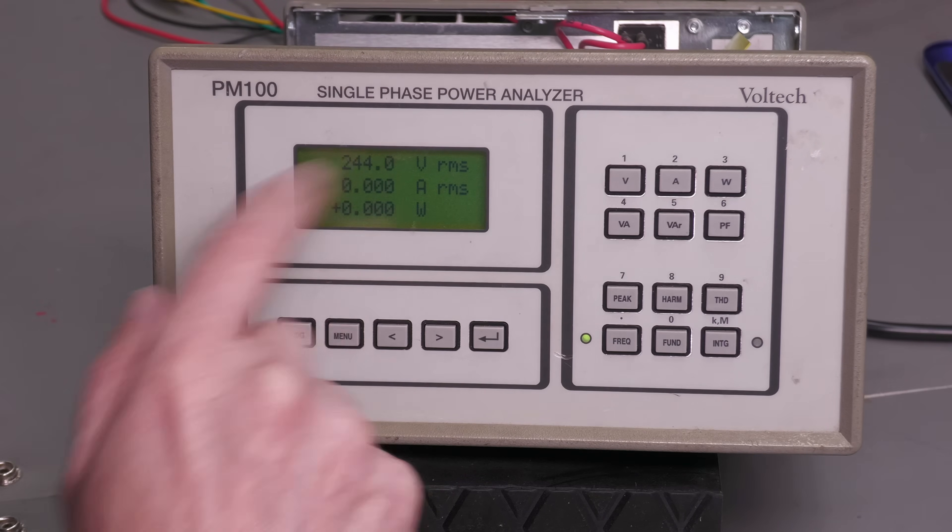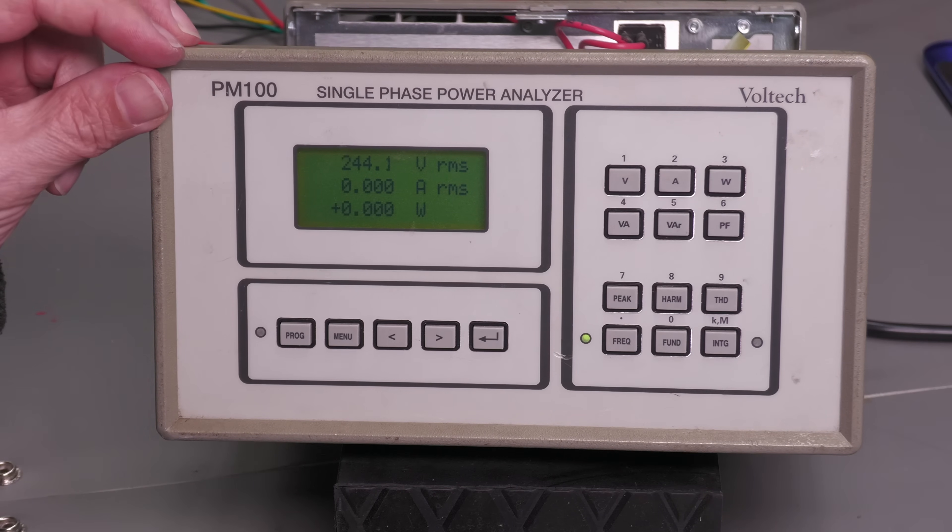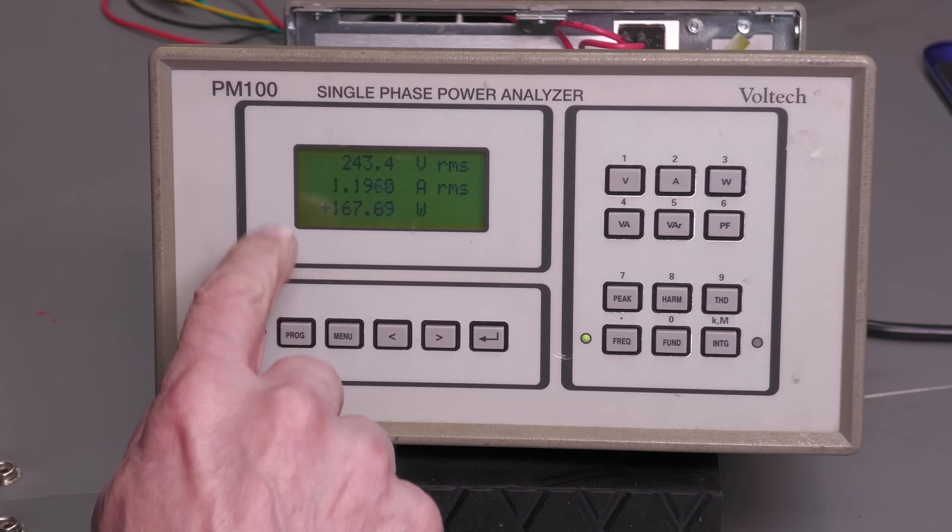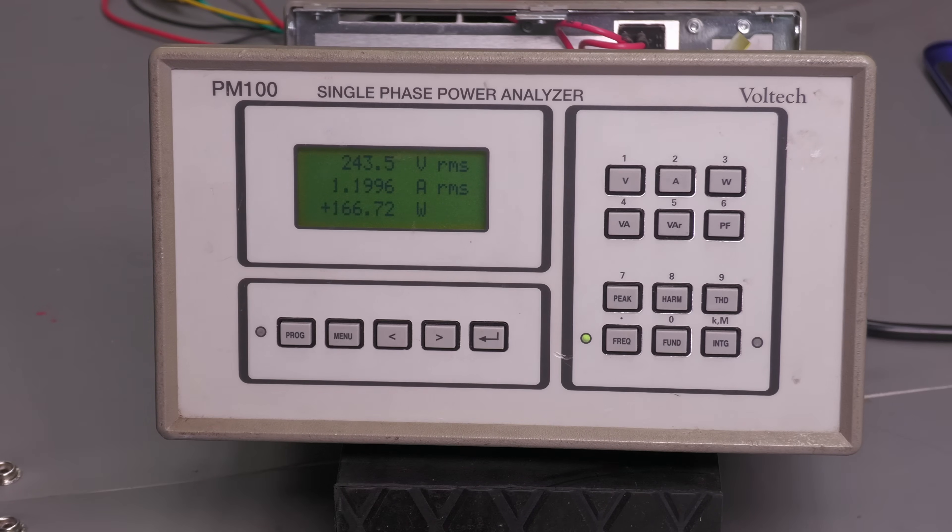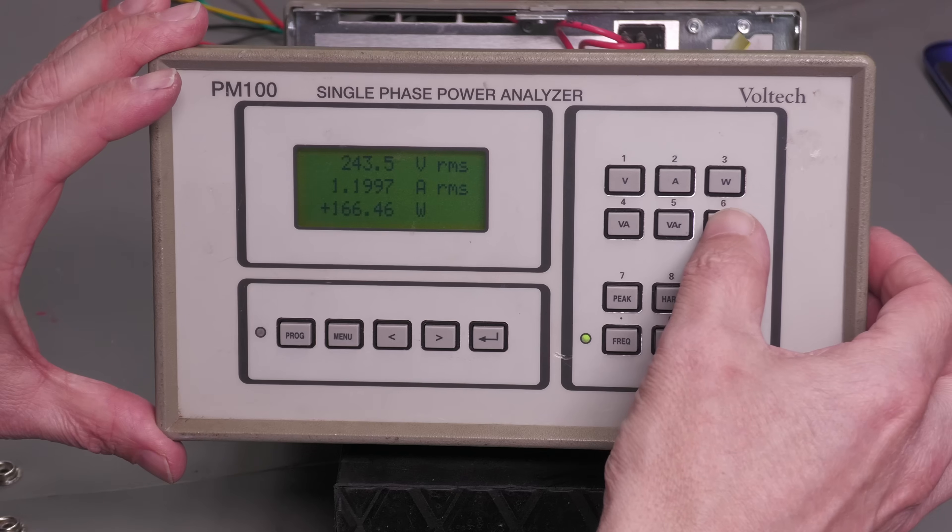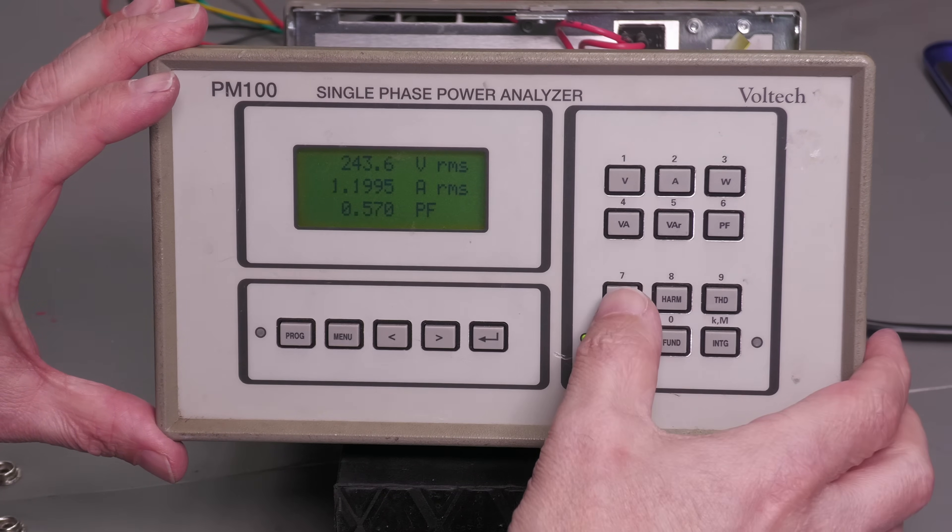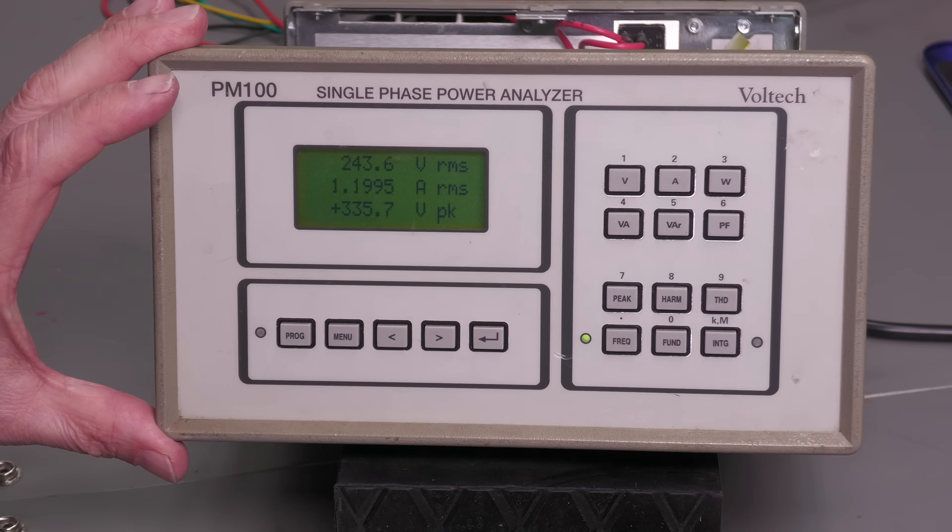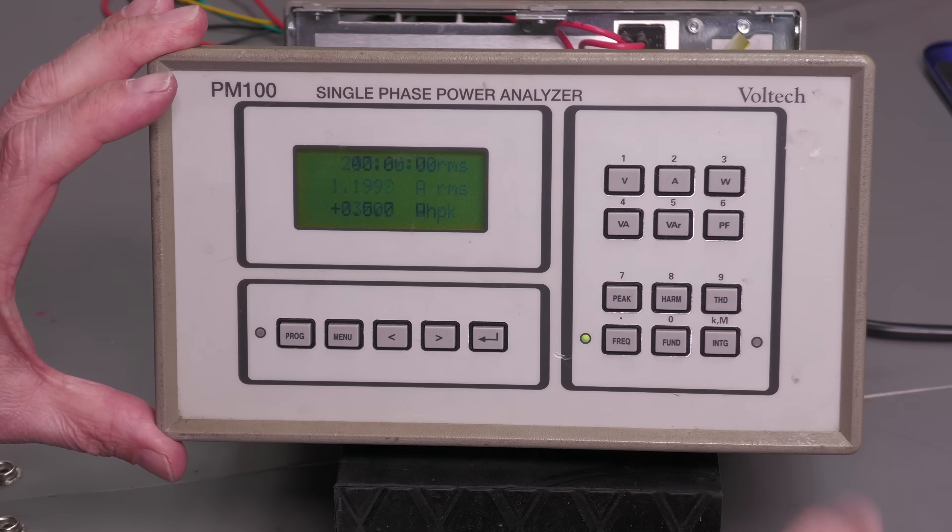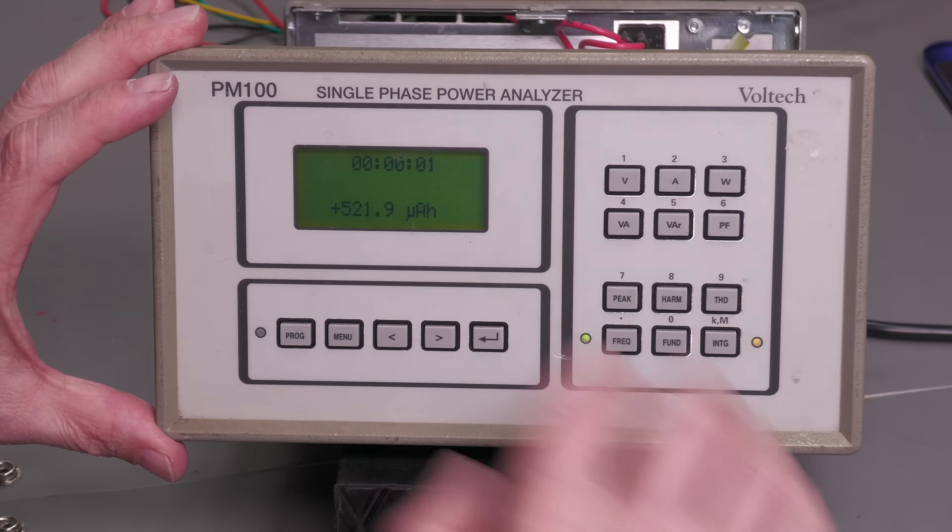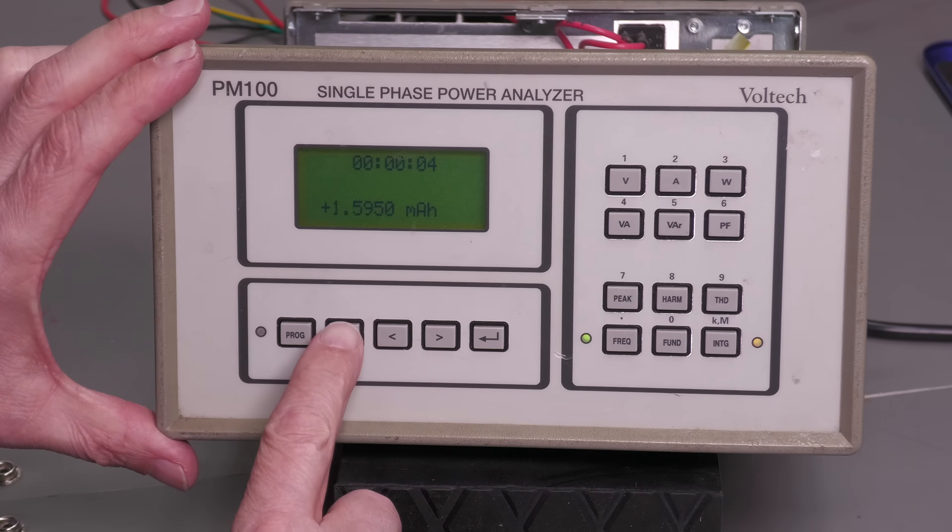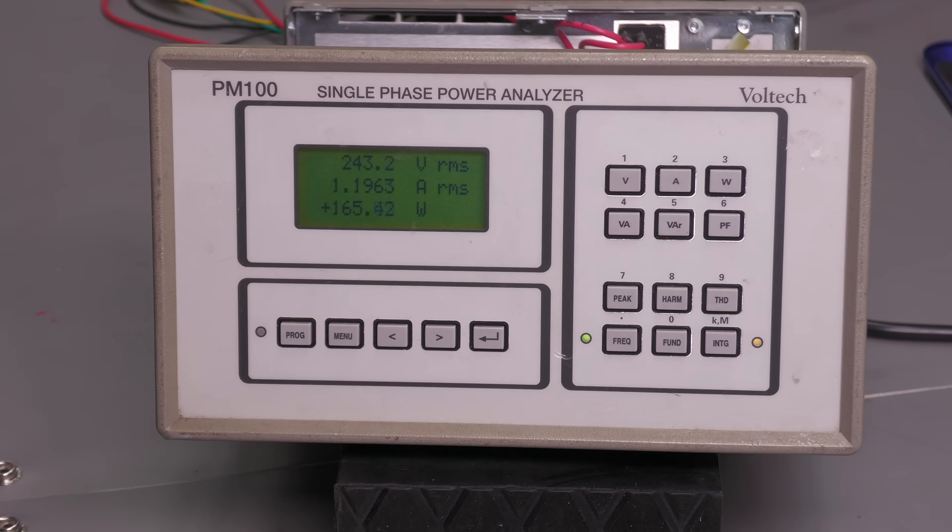244.0 volts today. So let me just switch on the heat gun. And yes, 1.2 amps there, about 166 watts. Perfect. Power factor 0.570. About some peak, yes, yes. Integrator, yes that's working. I think this unit's working perfect.